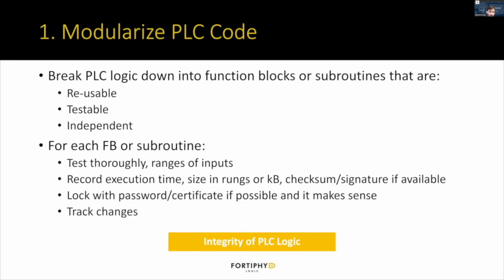When you break down the code like this, it also makes it easier to record execution times, the size of each function block or package or whatever, in kilobytes. You can also maybe get some checksums or signatures for each block, and then track changes over time to detect when it has changed, either from malicious or accidental changes. Another option that CODESYS actually does provide is you can lock each function block or program with passwords or certificates, and so that does add a lot more security. It does also add a lot more work for the operators and end users. So, if it makes sense, definitely try to do it. That is the best for locking those down. And so this practice is addressing the integrity of the PLC logic, helping to detect and prevent changes to the logic itself.